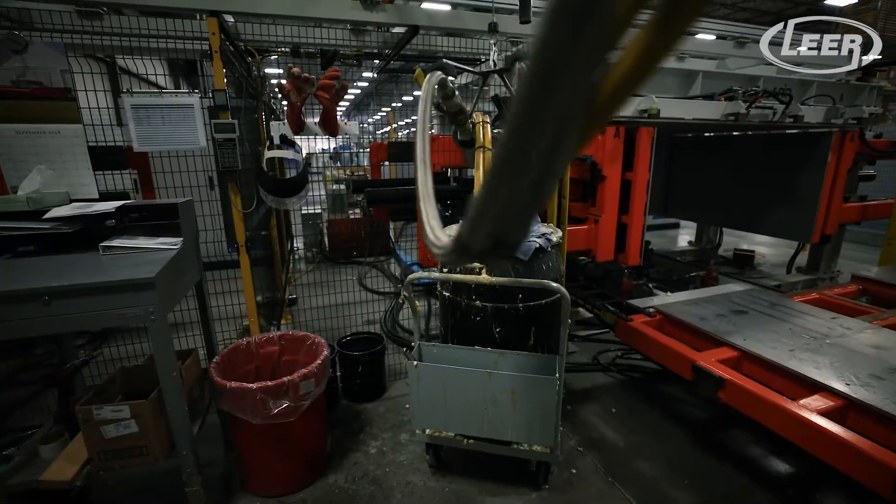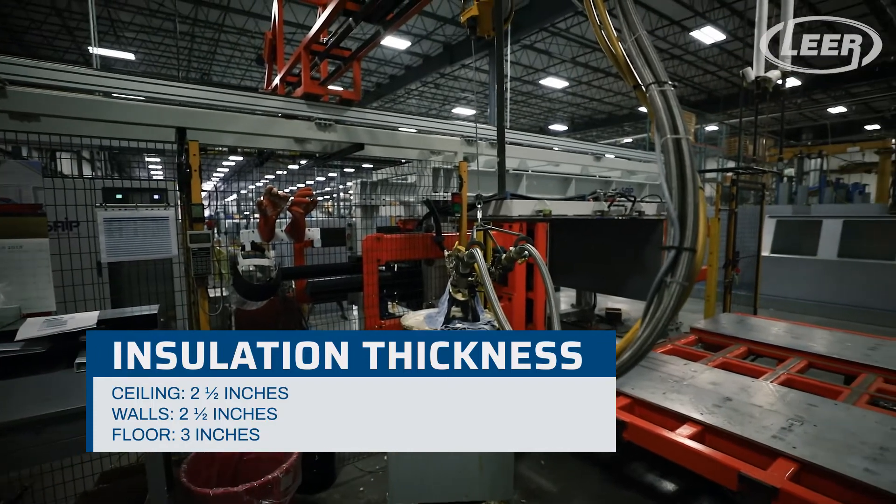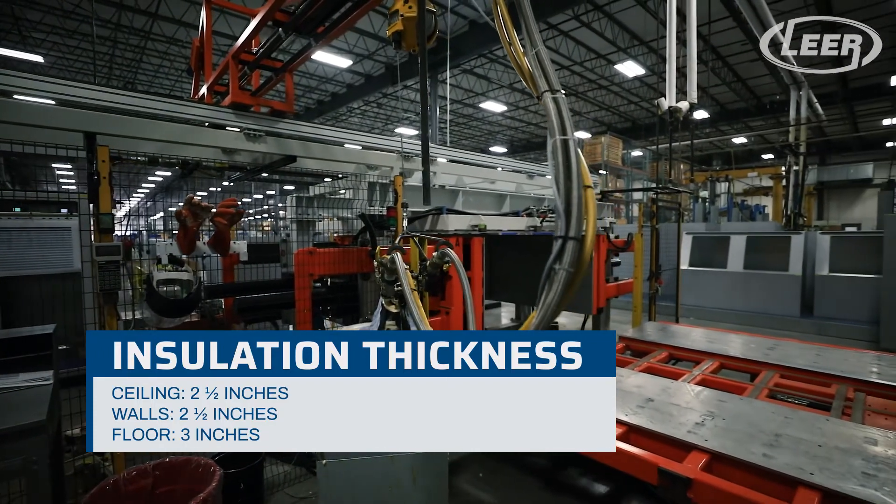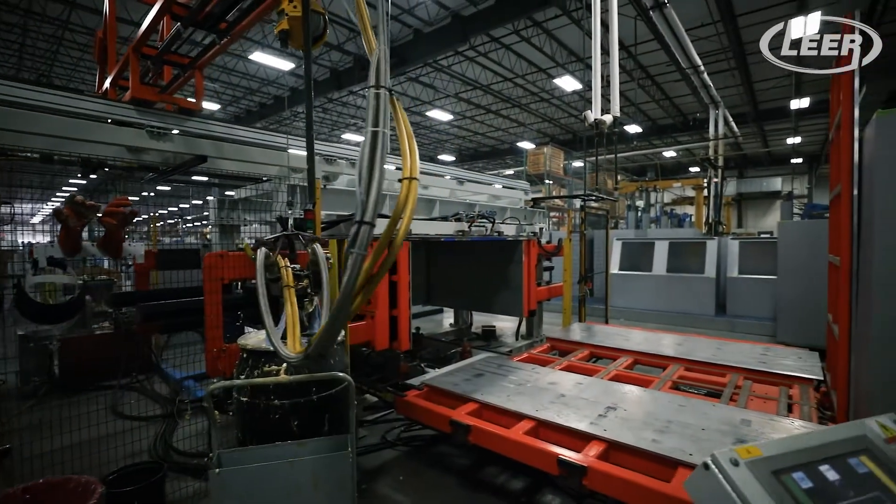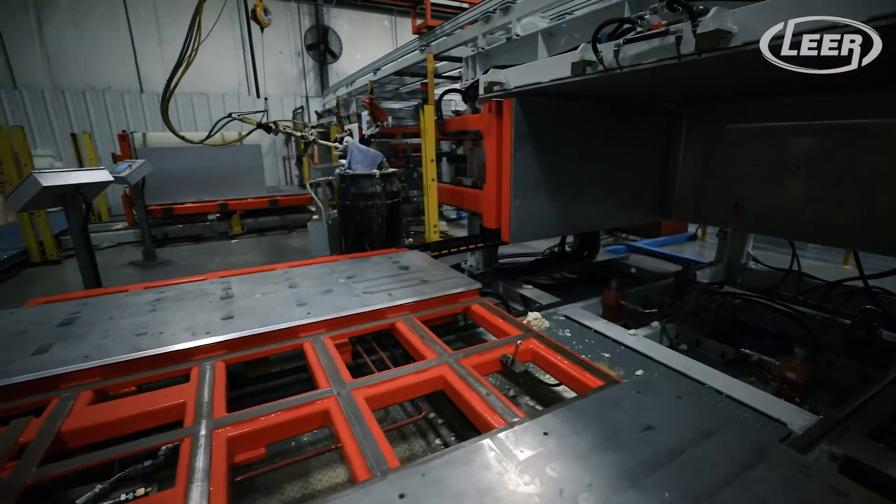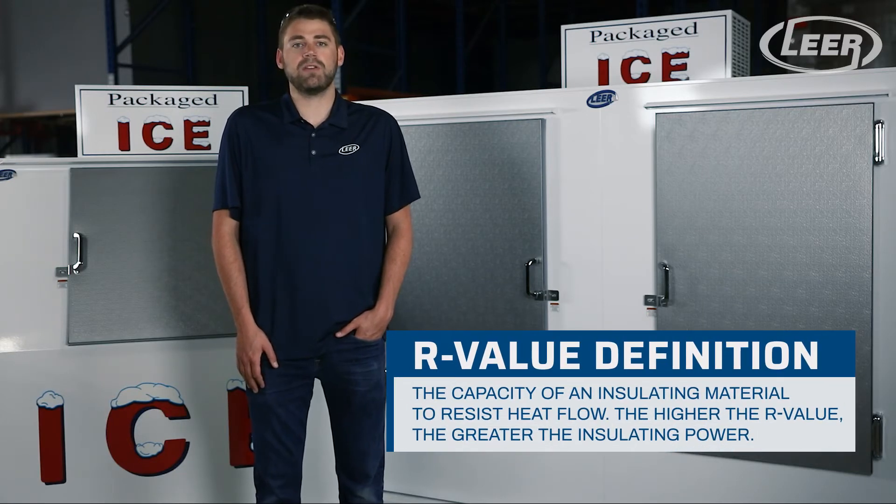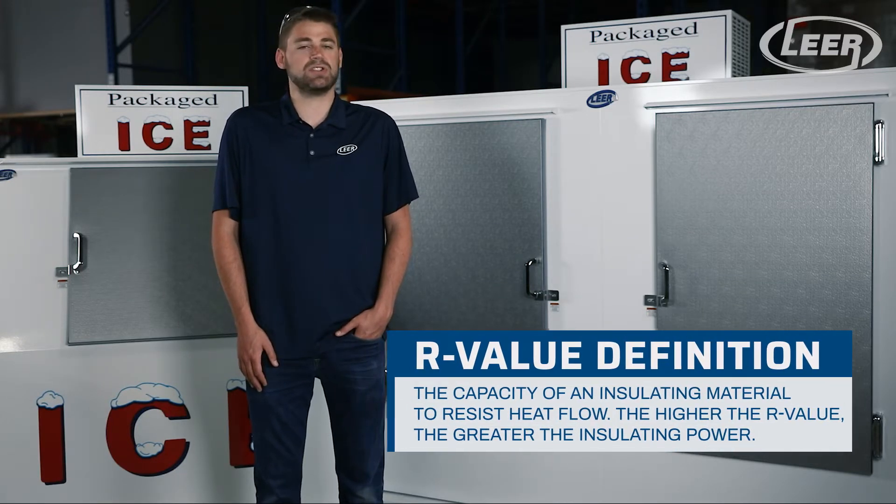In between the two layers contains the foam insulation. There's two and a half inches of insulation in the ceiling and walls and three inches of insulation in the floor. The insulation is a CFC-free foamed in place polyurethane. This ensures a high R-value, or in other words reduces heat transfer into the unit.